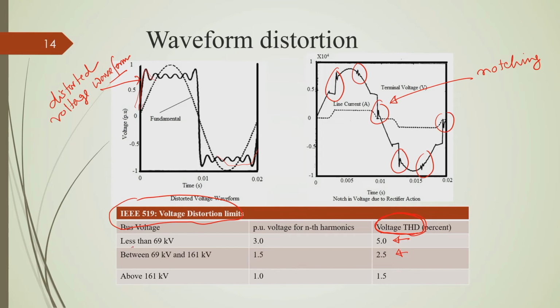For example, when we have a system lower than 69 kV, according to this standard voltage THD should be a maximum of 5% or lower, or acceptable voltage harmonics should be lower than 5%. Similarly, when we have a network with 69 kV to 161 kV, this THD should be 2.5% or lower. Similarly, above 161 kV this voltage THD should be 1.5% or lower.